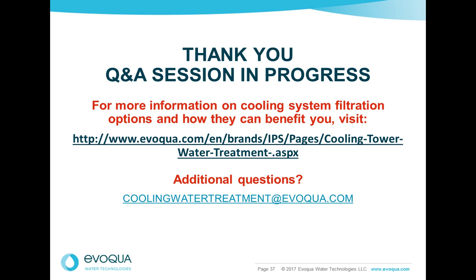This is Bob, and I've got a comment on it. If you're going to UV the entire cooling flow, it's going to be effective. But if you're thinking about UVing a side stream, if you only kill a percentage, they'll come right back and grow. Once they get back into the bulk water and mix with other bacteria, they grow at amazing rates. So a side stream on UV is just not effective. Great point, Bob.